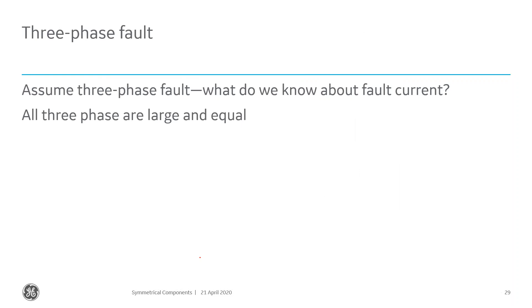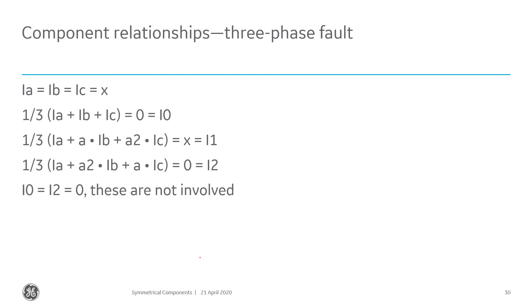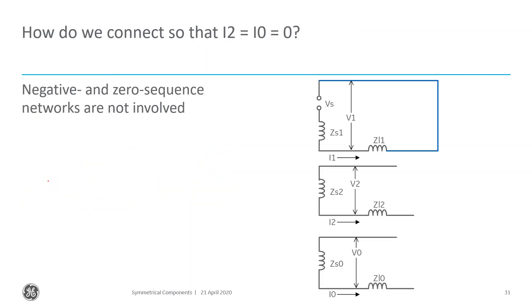For a three-phase fault, all currents are very large and equal. I-zero is zero, I-1 equals X, I-2 is zero — it's a balanced fault. Zero sequence and negative sequence currents aren't involved, so those networks aren't connected. For a balanced three-phase fault, only positive sequence currents flow and only the positive sequence network is involved. This is also what we expect for normal balanced load conditions.